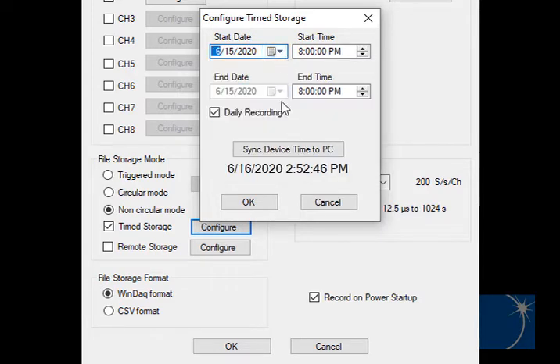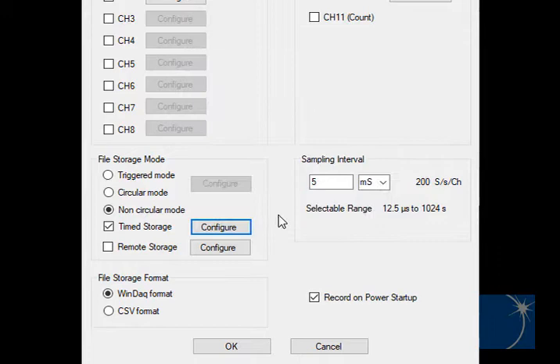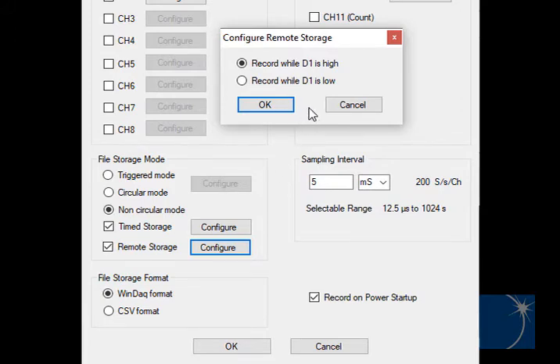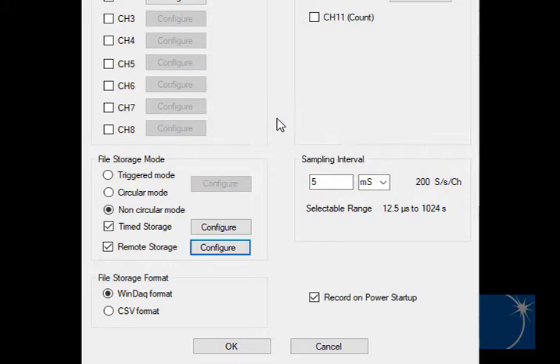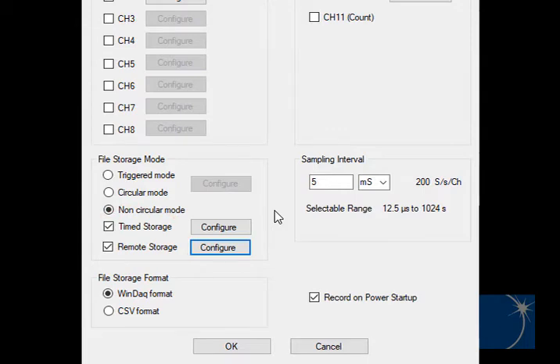You can make a single recording or record daily at the same time of day, or use remote storage to start and stop recording when the state of D1, the remote control pin, is true, TTL high or low. Timed storage and remote storage can be used in conjunction, but both conditions must be true to record data.